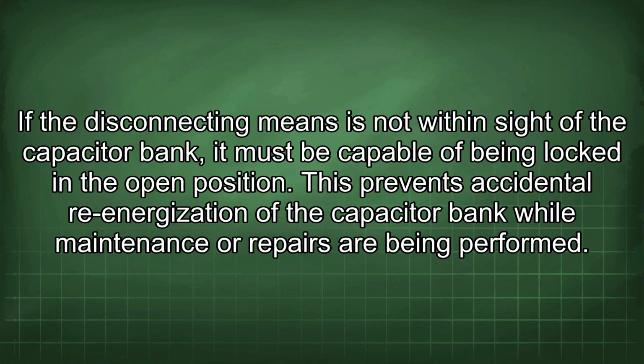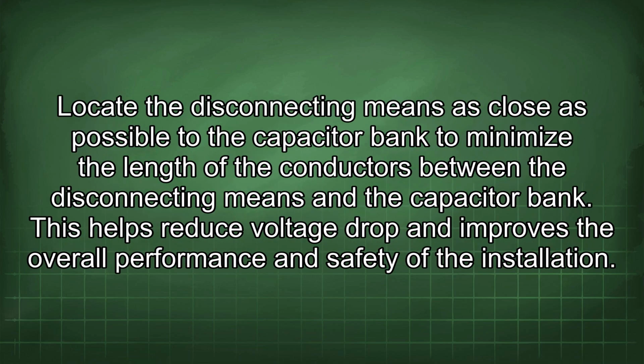If the disconnecting means is not within sight of the capacitor bank, it must be capable of being locked in the open position. This prevents accidental re-energization of the capacitor bank while maintenance or repairs are being performed. Locate the disconnecting means as close as possible to the capacitor bank to minimize the length of the conductors between the disconnecting means and the capacitor bank. This helps reduce voltage drop and improves the overall performance and safety of the installation.